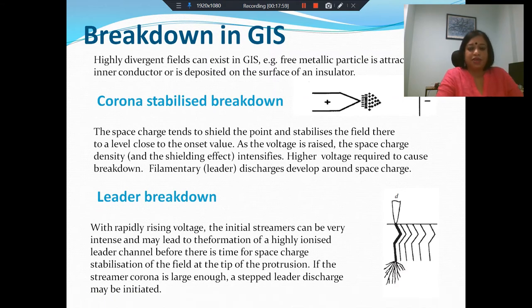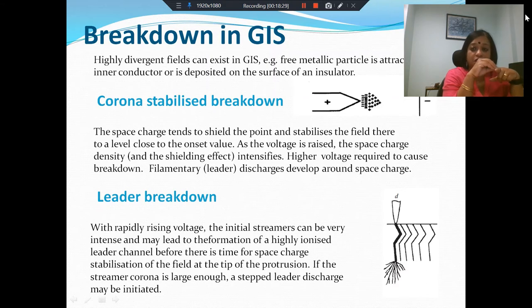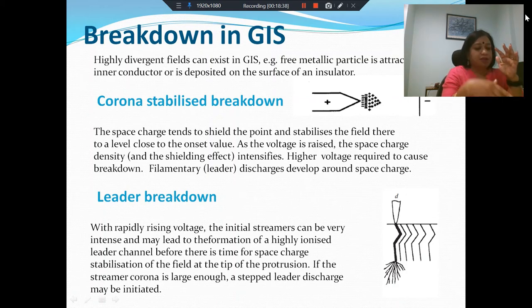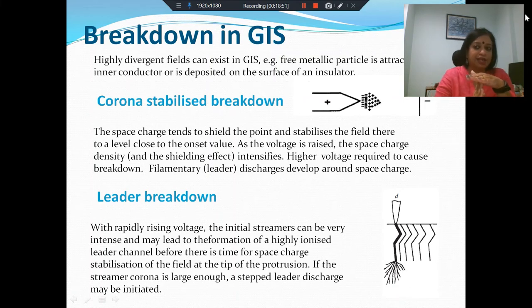When talking about breakdown in gas insulated substations, remember we have highly divergent fields possible inside a GIS. Normally a GIS has a coaxial configuration — the conductor in the middle at the center, the metallic enclosure on the outside, and the insulating medium in between. However, highly divergent fields are possible in the sense that the inner conductor may have metallic particles, or on the surface of the insulator. You have spacers to hold the conductor in position periodically — just like transmission wires hold up overhead lines — which provide mechanical support to the inner conductor. There might also be metallic particles deposited on the insulator surface, manufacturing defects, protrusions from the conductor, and free particles causing local divergent fields.